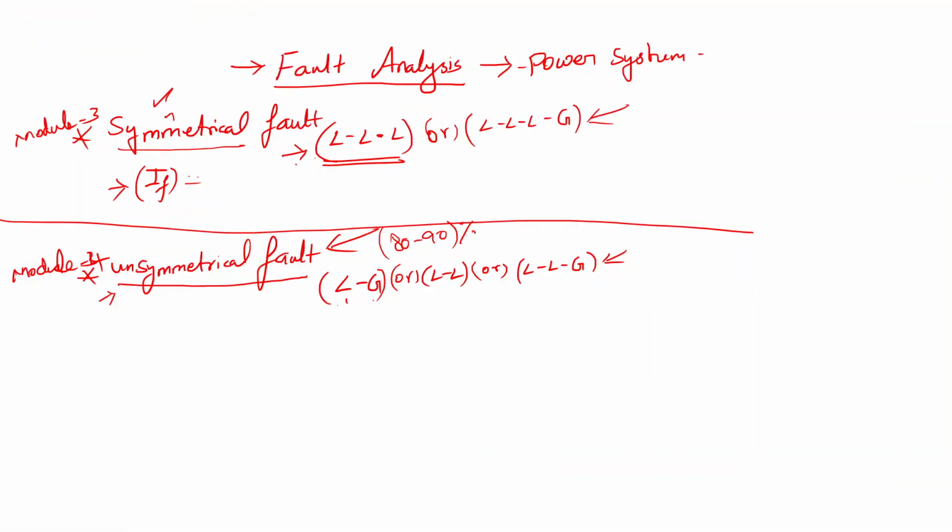Okay, so the load is not considered, or load current will not be there, because all these three are shorted. So there is no use of considering the load while calculating the fault analysis. That is one important thing you need to consider while doing the problems. If you want to calculate fault analysis, we can ignore or neglect the load during the fault.